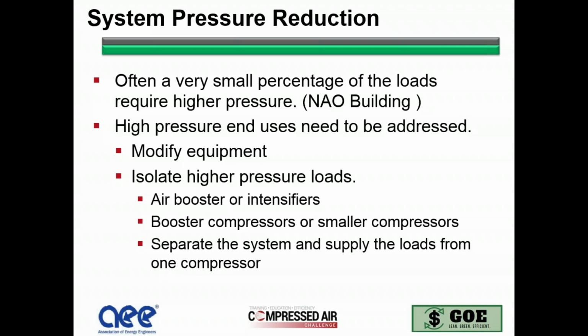and you'll find that a lot in production. Many times the production equipment is spec'd at a higher pressure, either for footprint size or because that's what the manufacturer does so they can use smaller cylinders. When you do that, you have to be aware of it because, again, that drives the entire system. So you have to maintain that pressure even if it's a small percentage. And what we're saying is do something about it. So you want to take those high pressure end uses and address them. If you can, you want to modify the equipment, or add booster compressors or smaller compressors, or even separate it into a separate system, or feed it from one of the supply compressors you have. There's multiple ways of doing it, but the key here is don't let it drive the system. Take advantage of being able to lower those pressures.